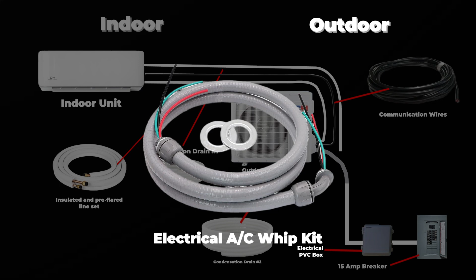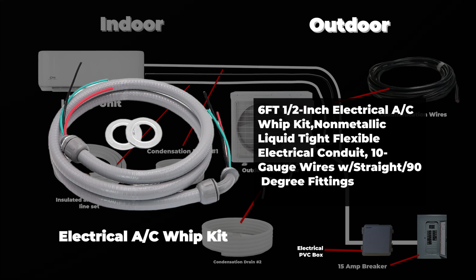For the power connection, we have a 6-foot, half-inch electrical AC whip kit, non-metallic, liquid-tight flexible electrical conduit, 10-gauge wires with straight and 90-degree fittings, ensuring a safe and durable setup. Take note of this diagram, as it will be applied in part 2.